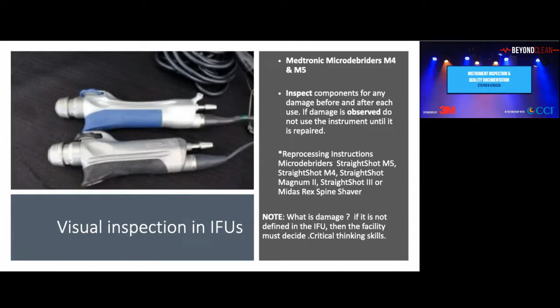How about this? Visually inspect. Inspect the handpiece to make sure there's no visible soil, damage, signs of wear, and/or corrosion. So how do you define that? What is corrosion? What's wear and tear? This one says inspect components for any damage before and after each use. If damage is observed, do not use the instrument until it is repaired. What is damage? If it's not defined in the IFU, then the facility must decide. Critical thinking: what is damage? Or maybe you write the manufacturer to get a little more instruction on what damage is or what you need to look for.